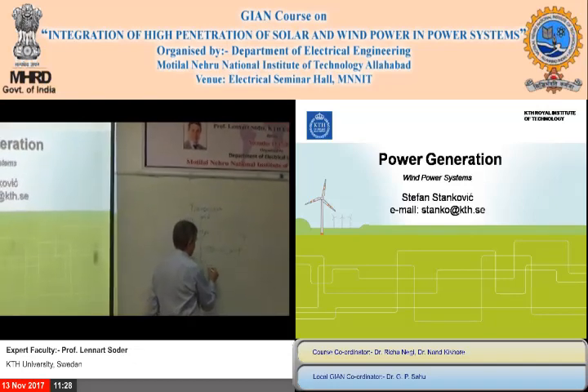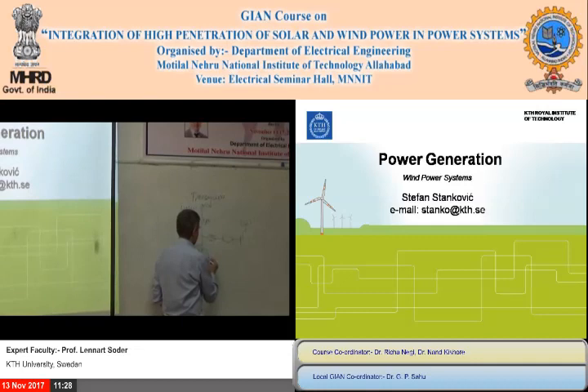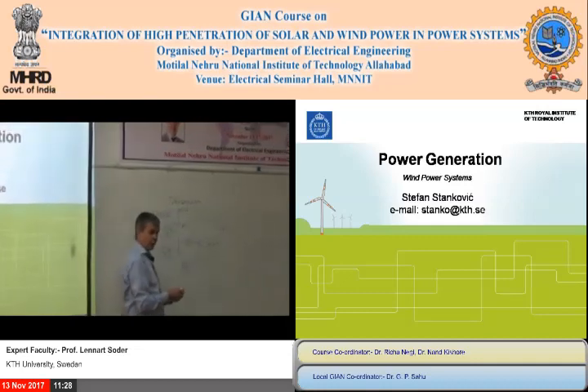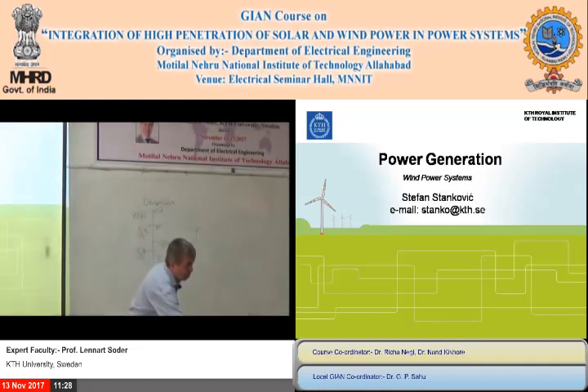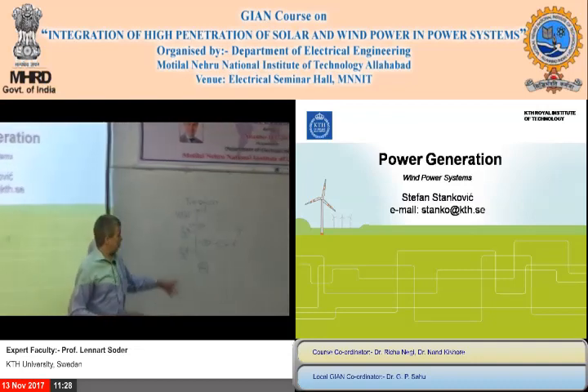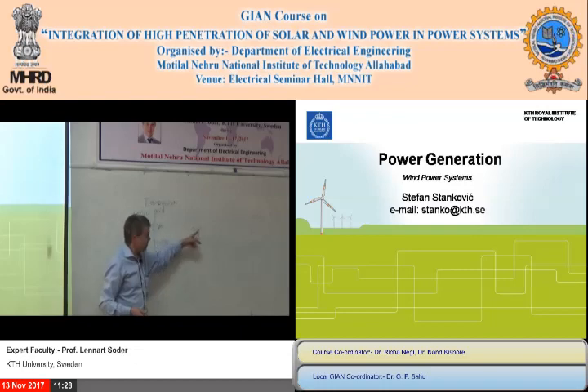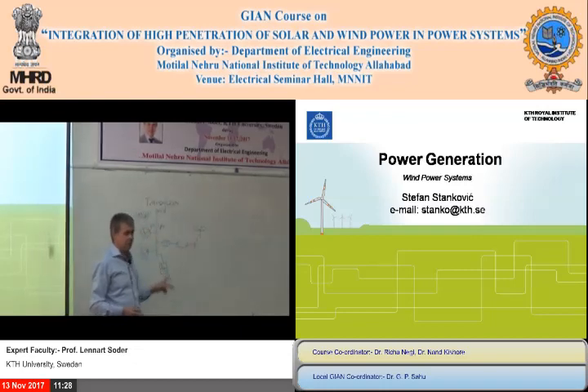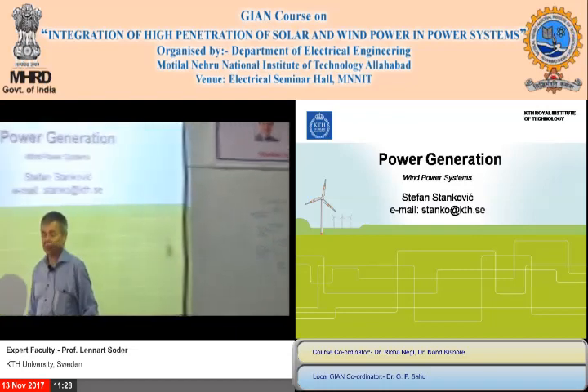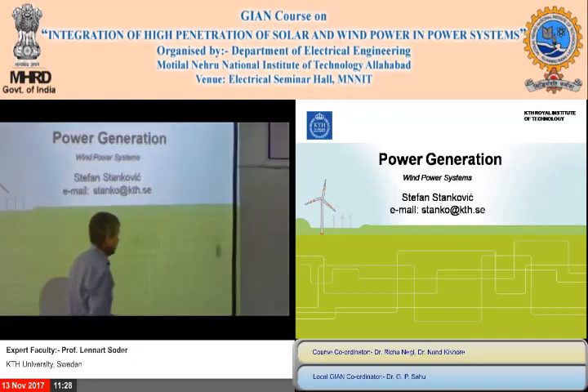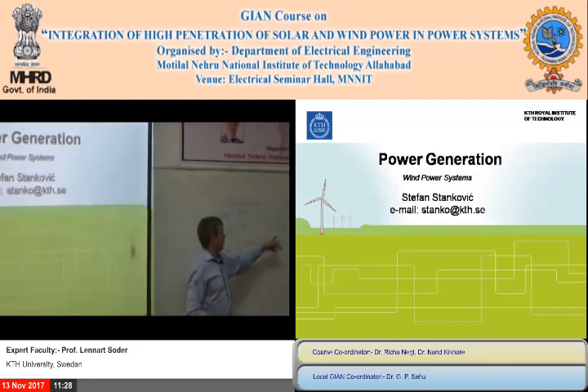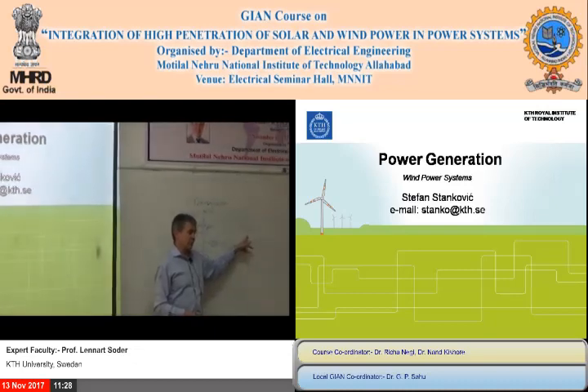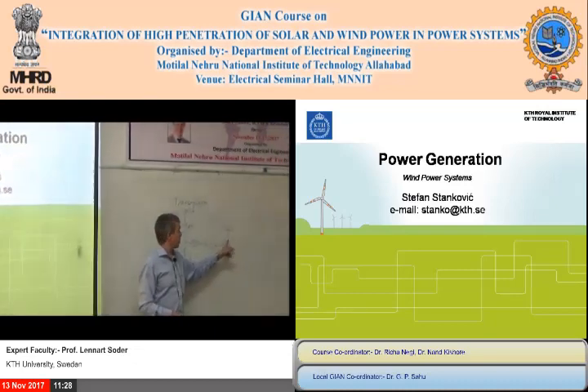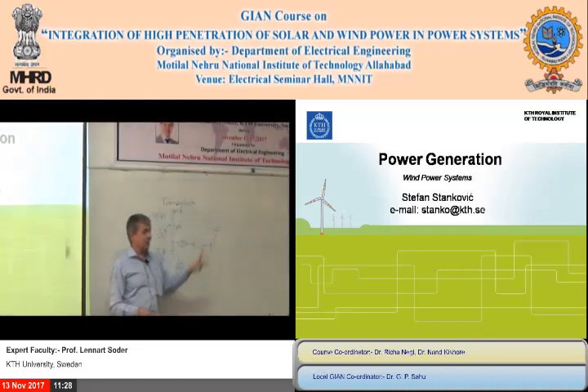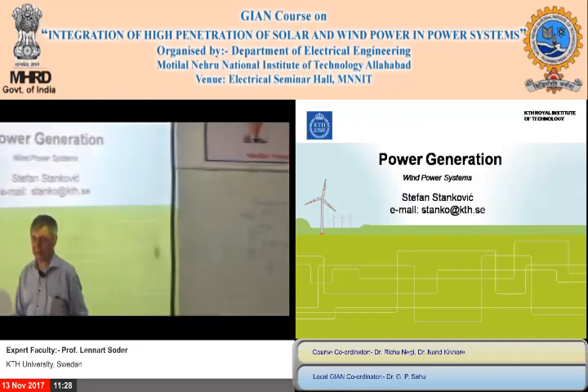What you can do here is put in static var compensation, power electronics, VSC, or capacitors, inductors, and so on. But the question is whether you need this if you can do it with the ones you already have there - then you don't need this one perhaps. The standard today is that this one will only send out P, cos phi equal to 1, so we normally only send out the active power from that one. That's the standard today.